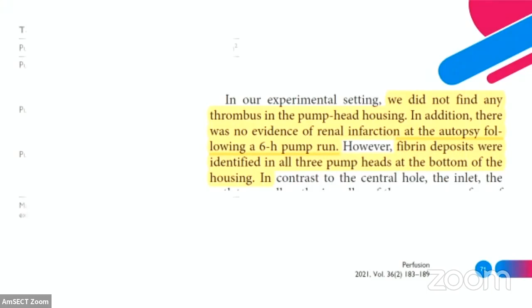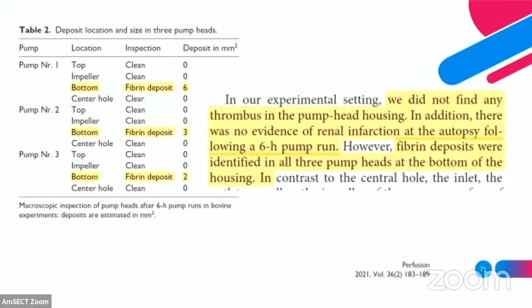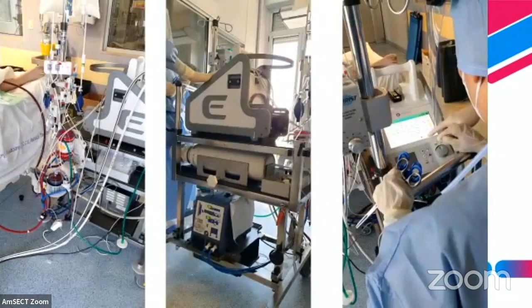And what about thrombus and fibrin deposit? You can see here that the center hole was clean, the top of the impeller was clean, the top of the pump was clean, the impeller was clean. There was just fibrin, no thrombus, but a fibrin deposit in the tested pump, a very small fibrin deposit. Obviously, it is not a miracle pump. It's always a real object, with physics that can be applied. However, the fibrin deposit was very low compared with other kinds of pumps, and this is a strong point to start.